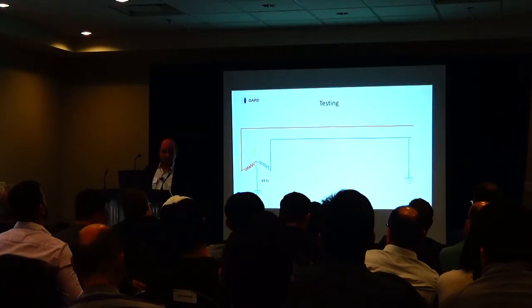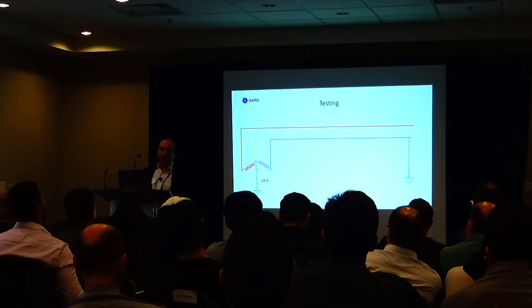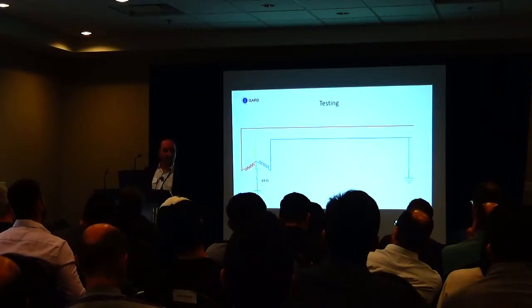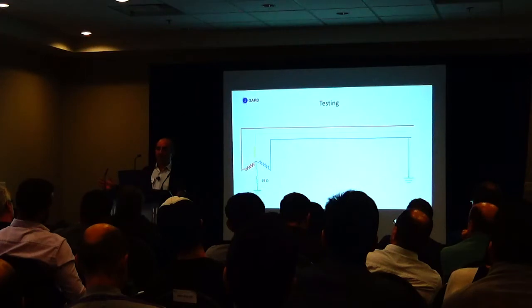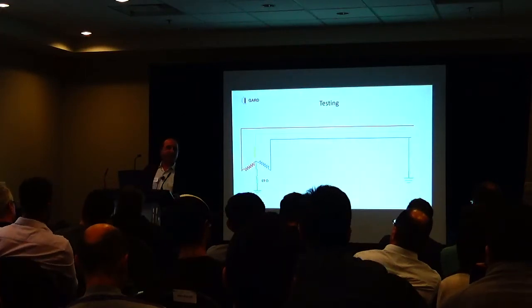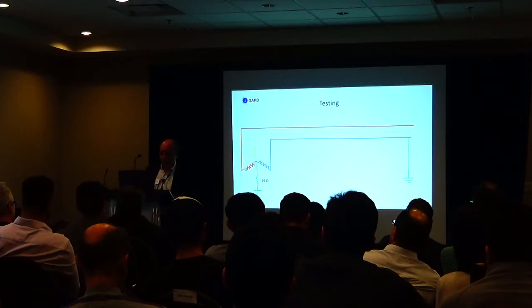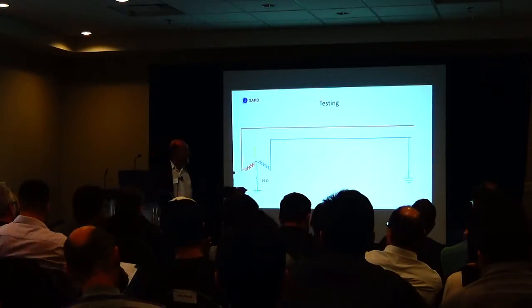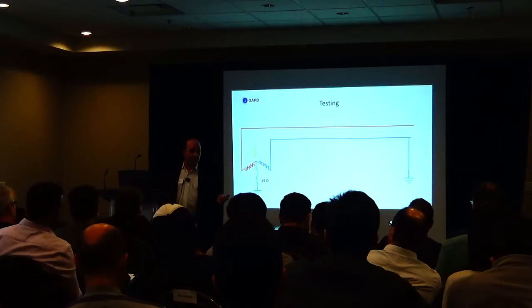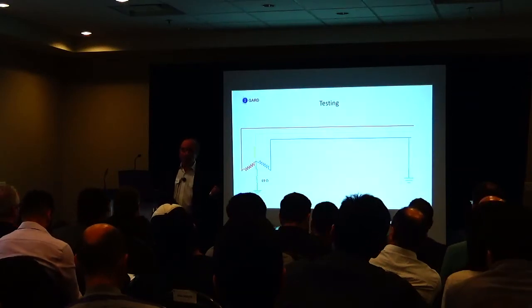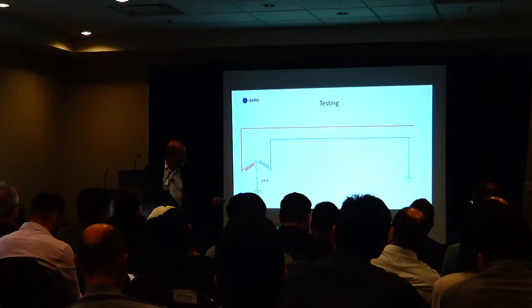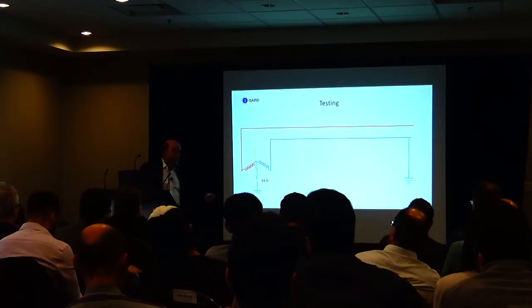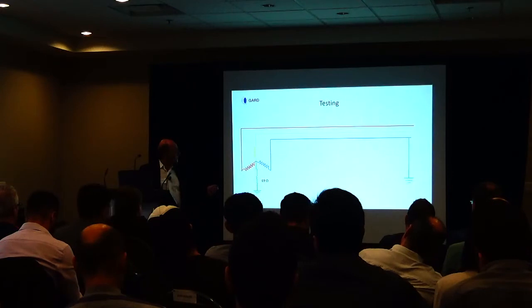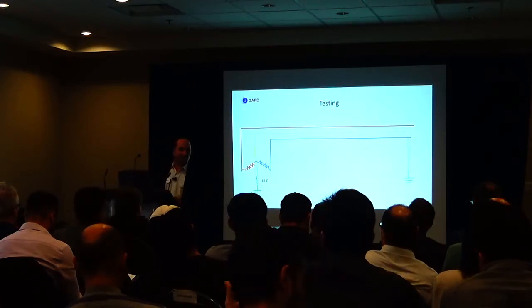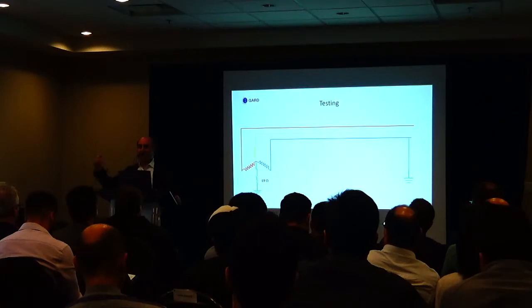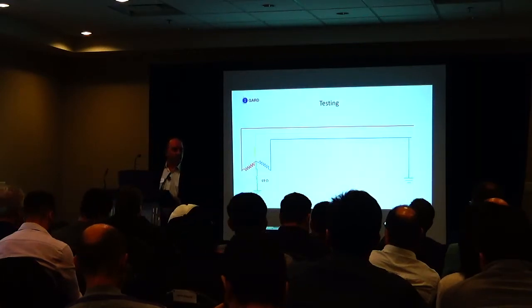When it comes to testing, we've had a lot of issues with testing high resistance grounding systems. There are so many times that people get things wrong, and I'm here to tell you the right way of doing it. You can put a fault on the system. What we do when we test and commission a high resistance ground system is ensure that when we put a fault on the system, not only do we detect that the fault is there, but we detect that this phase and this phase elevate to the full phase-to-phase potential, and we ensure that the connected load is compatible with the resistance ground in the system.